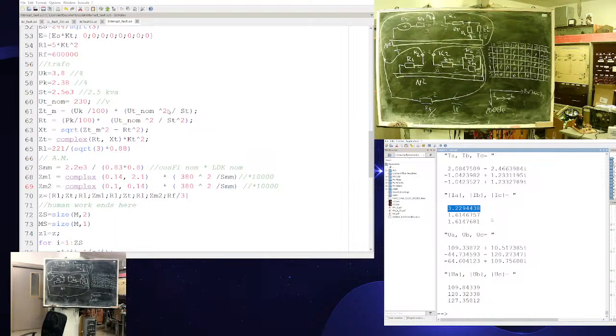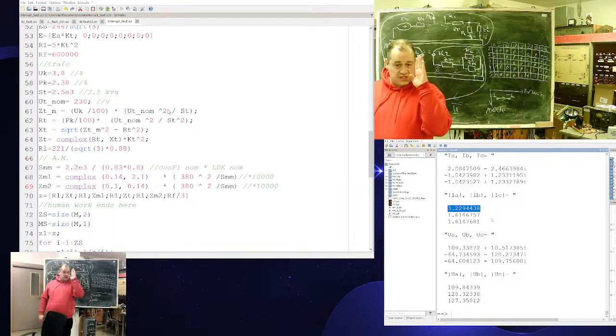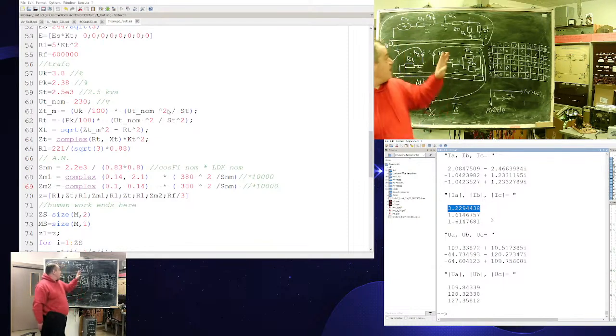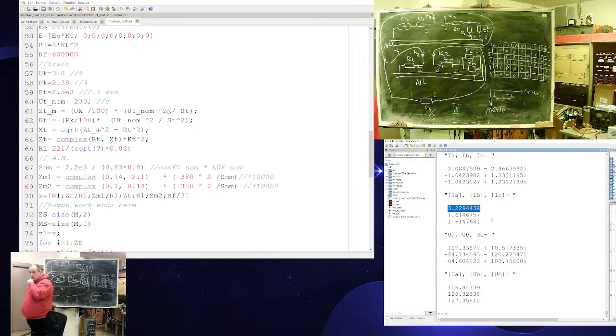This transformer is of group 11. This means that if I take A phase voltage on the star side as at 12 o'clock, A phase voltage at the delta side should look at the number 11, meaning 30 degrees forward, so 30 degrees leading. 30 degrees leading is okay, so A phase is A phase.